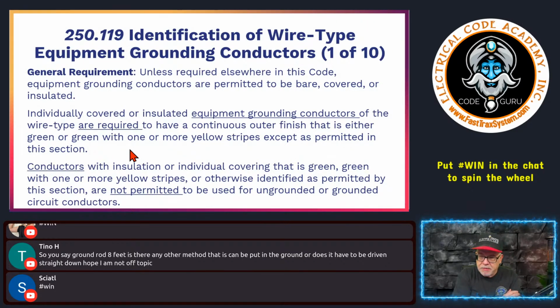But other than that, it's important to remember that if you see an equipment ground that's insulated, because remember, it's allowed to be bare, but if it's insulated for whatever application or whether the code tells you to insulate it, then it would be green or green with yellow stripes, depending on the application, okay?